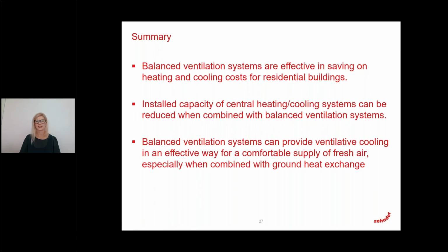And to summarize this session, balanced ventilation systems are effective for heating and cooling costs in residential buildings. We could set our systems in a way that takes the most of the technology and therefore saves some costs, with a system that is built considering all the seasons. Installed capacity of central heating and cooling systems can be reduced when combined with a balanced ventilation system. And balanced ventilation systems can provide ventilative cooling in an effective way for a comfortable supply of fresh air, especially when combined with ground heat exchange.